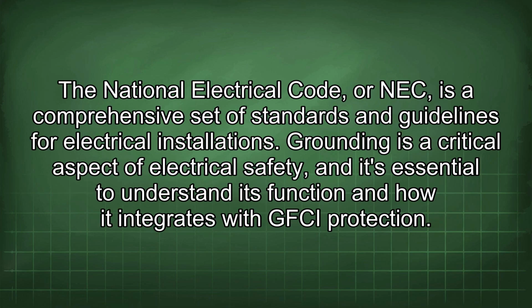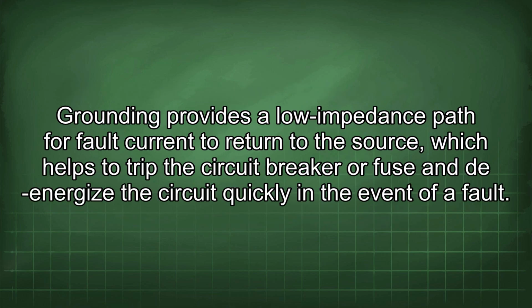The National Electrical Code, or NEC, is a comprehensive set of standards and guidelines for electrical installations. Grounding is a critical aspect of electrical safety, and it's essential to understand its function and how it integrates with GFCI protection. Grounding provides a low impedance path for fault current to return to the source, which helps to trip the circuit breaker or fuse and de-energize the circuit quickly in the event of a fault.